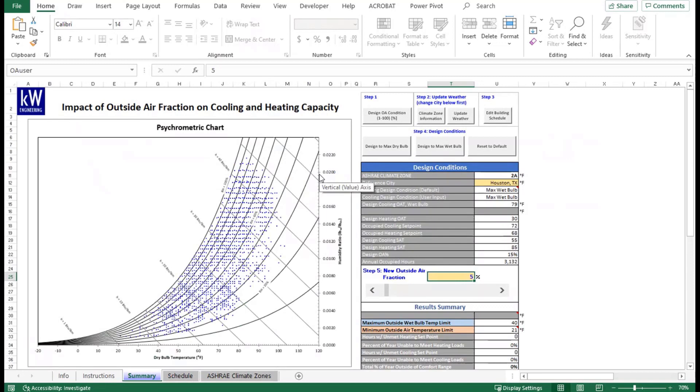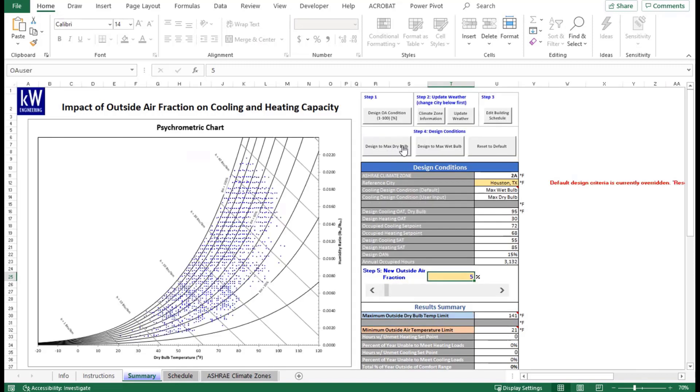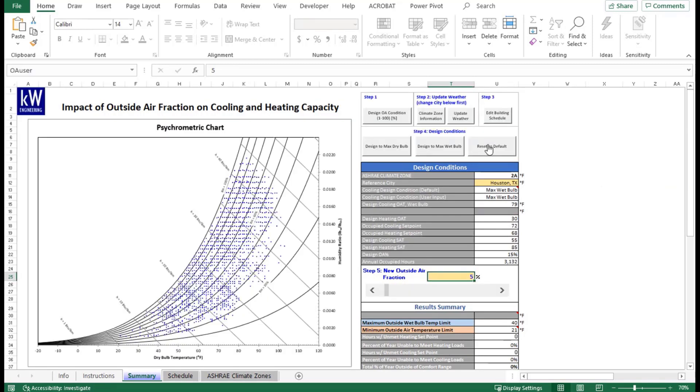The next step is to look at the design conditions. Different buildings will have different design conditions for their analysis. For the city of Houston, we will be using the max wet bulb condition. If you wanted to switch it up to see how it impacts if your particular building was designed for sensible load and not to take into consideration humidity, you can do that by overriding the design condition here by designing to max dry bulb. You can switch back over to max wet bulb or reset to default if you don't remember what the appropriate one is for that region.